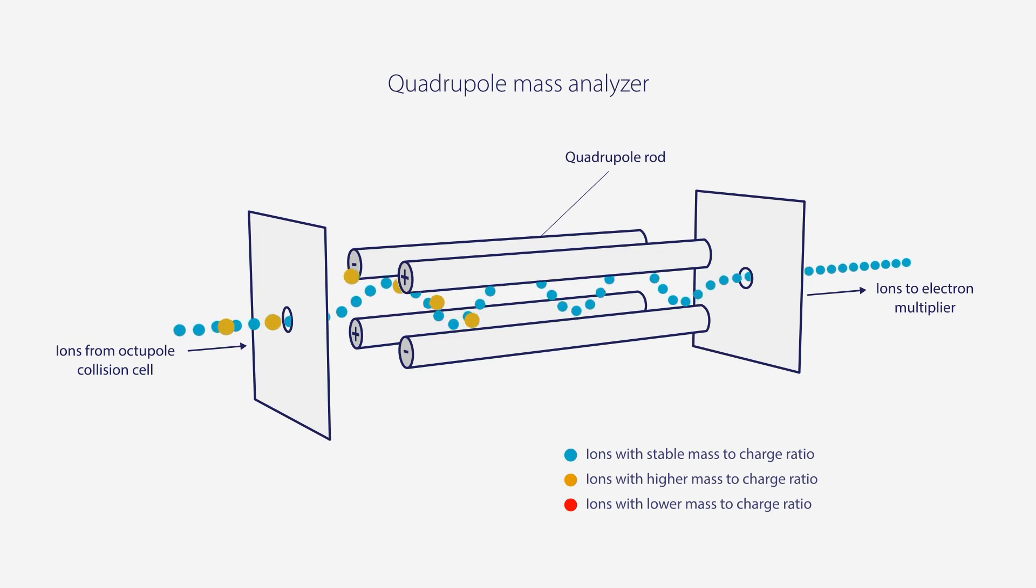Ions with higher or lower mass to charge ratios will have unstable trajectories through the quadrupole and either collide with the rods or exit the region between the rods and be removed by the turbopump. Ions with unstable trajectory do not reach the detector.